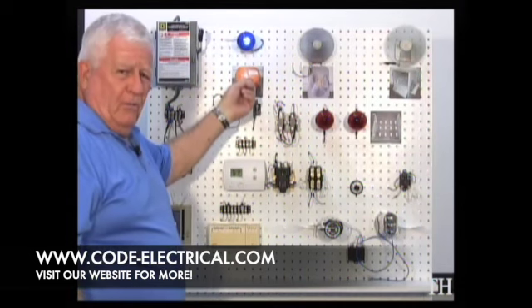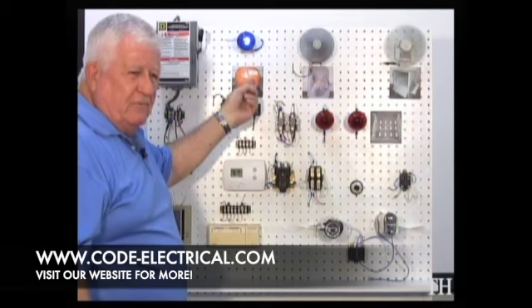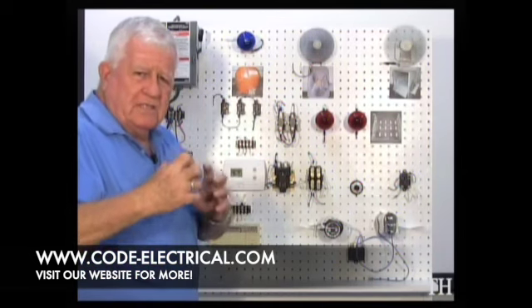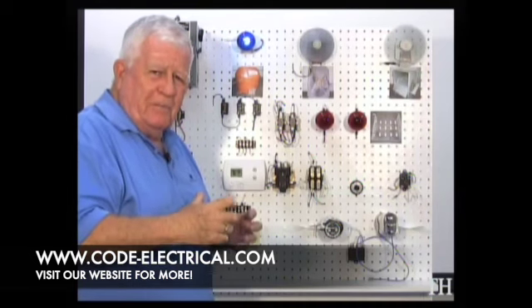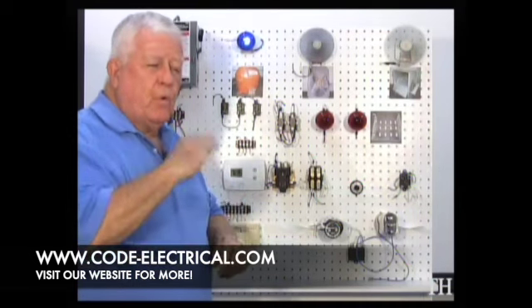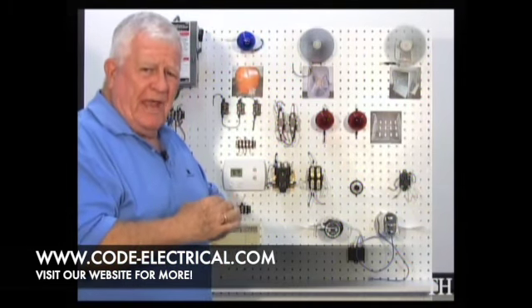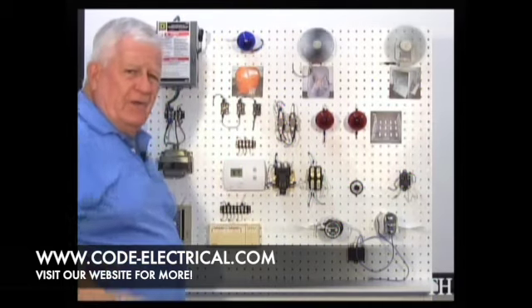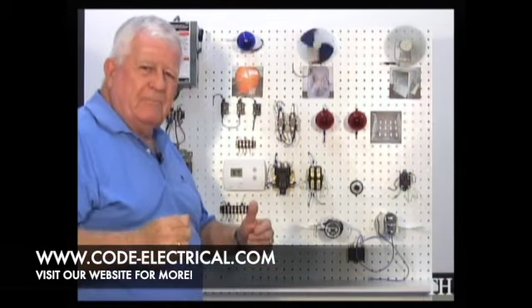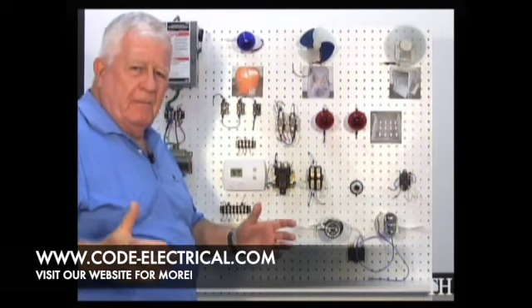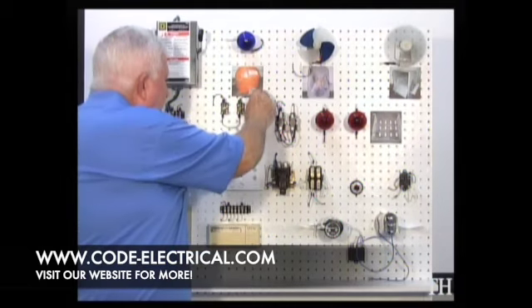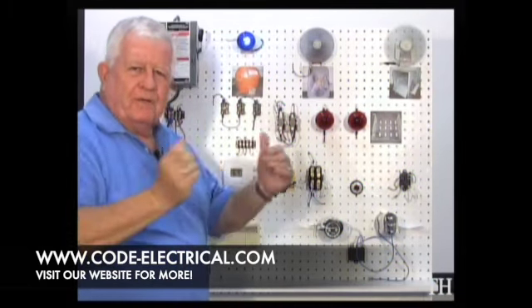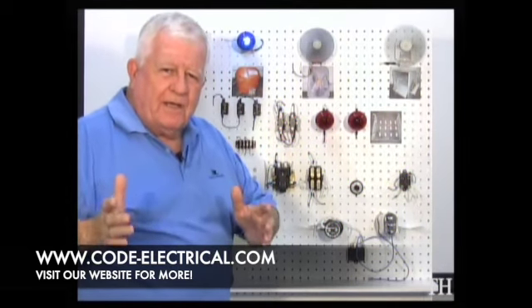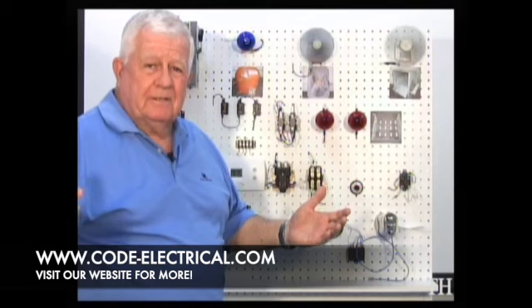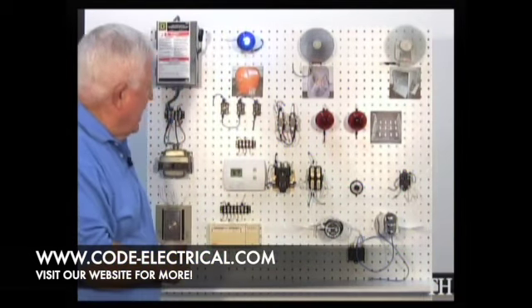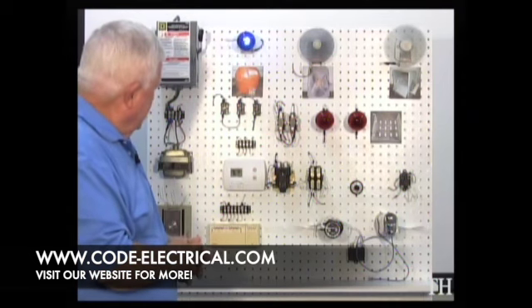Or guess what? The thermal overload. It's a protection for the compressor, to keep it from, say it locks up, or the bearing starts dragging, or you got a resistance on it mechanically. This thermal overload says, man, it's hot in here. Something bad's going to happen. Shut her down. Shut it down now. It shuts the compressor down to keep from burning it up, from damaging it. They're expensive. But what you have to learn as a technician is all three of those are safeties. They're to protect that compressor. Well, if that compressor isn't running, it's up to you to determine what happened. Why isn't it? That's your job as a technician, to go through all this stuff and to learn it.